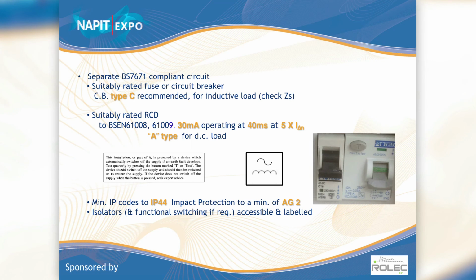Also, you need an A-type RCD. Most RCDs we use are only susceptible to AC current. This car is a DC rectified battery. If there's a fault on the car, what we don't want is it putting fault currents back onto the system. So the RCD we employ must be able to read both AC and DC currents and trip on them both. So as you can see from here, we've got a C-type breaker, and that there is a 0.03 and it's an A-type RCD.